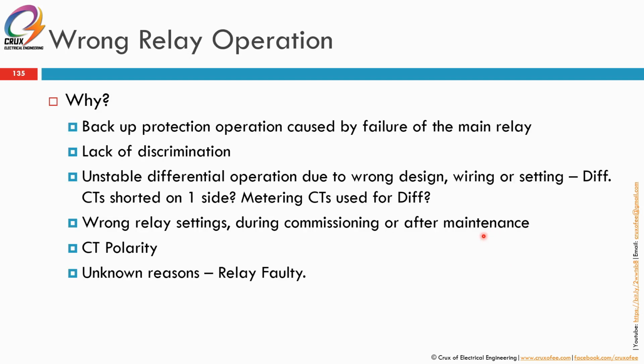Alright. Why can a relay wrongly operate? Number one, backup protection operation caused by failure of the main relay. For example, the motor relay should have tripped, but it did not trip. You find the motor burnt, but why did the incomer trip? Maybe the incomer became the backup protection, so you have to note that. That one is not a wrong relay operation. It's actually a backup protection because of the failure of your main relay, the motor relay.